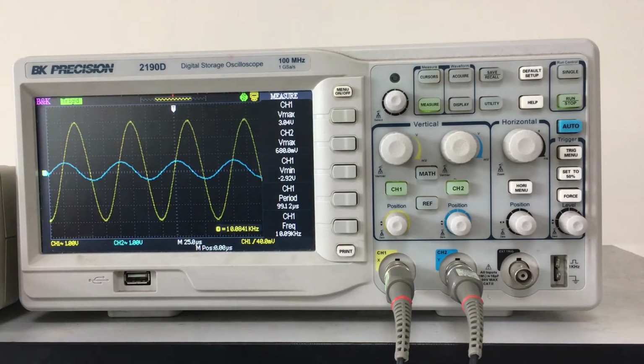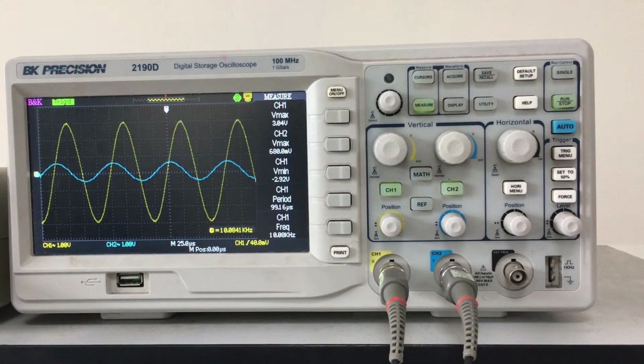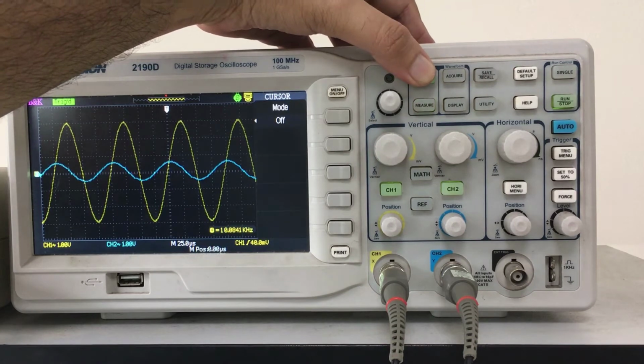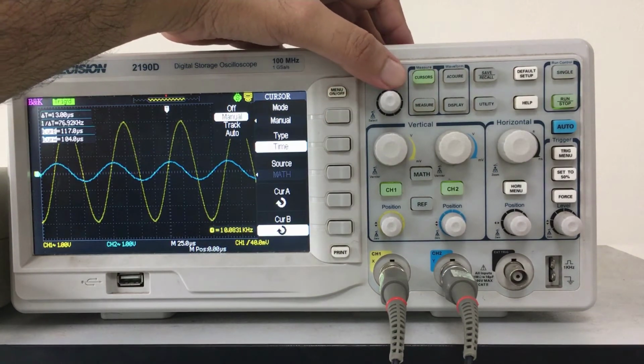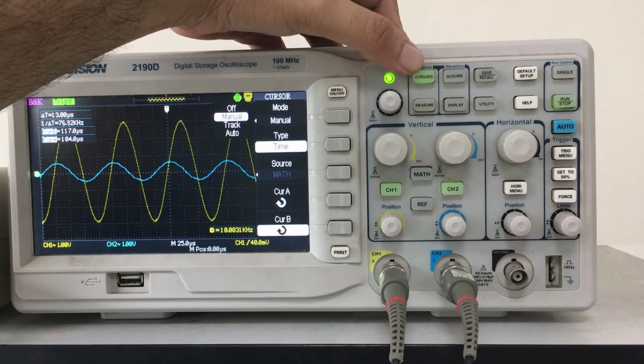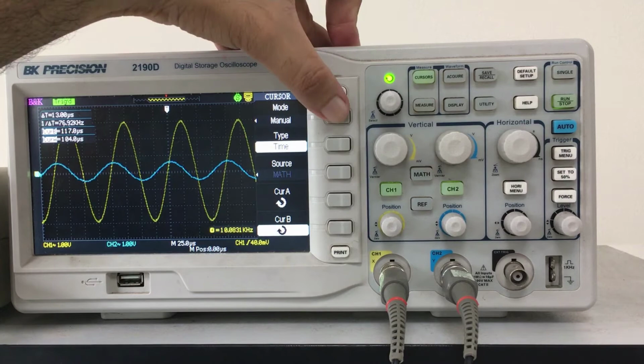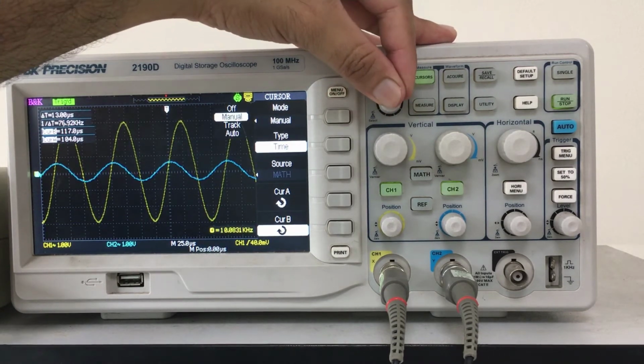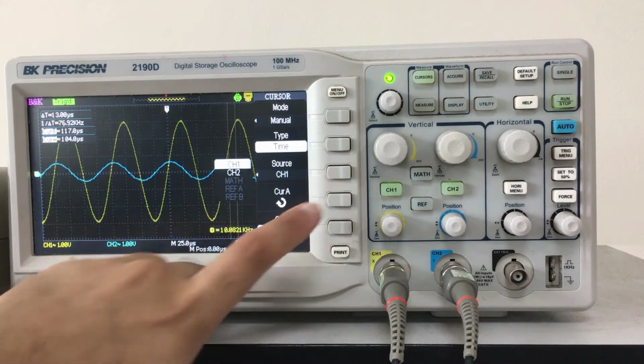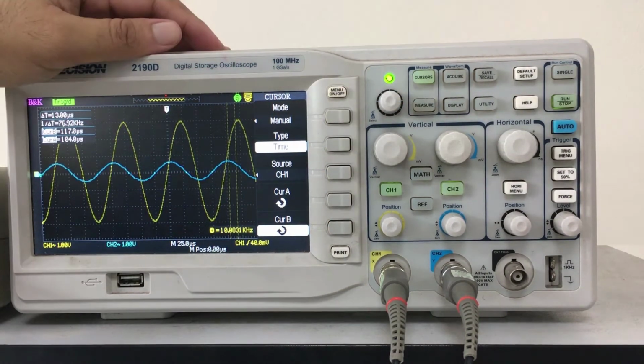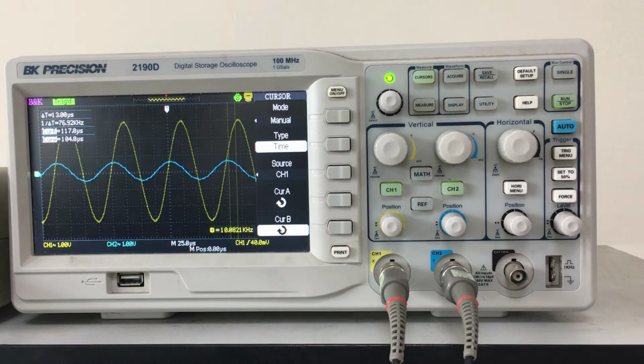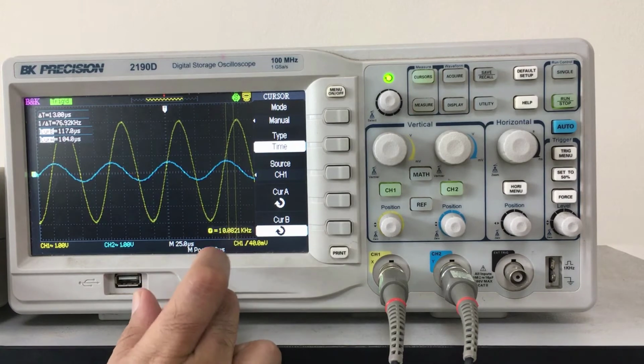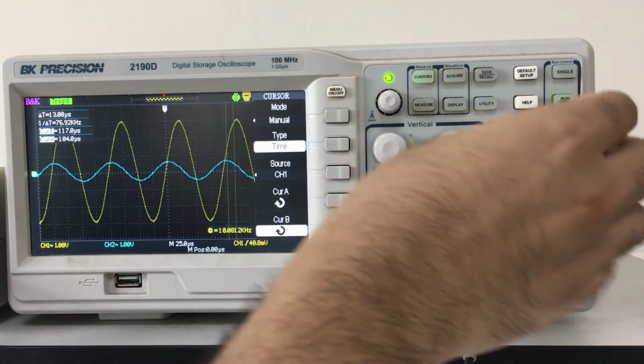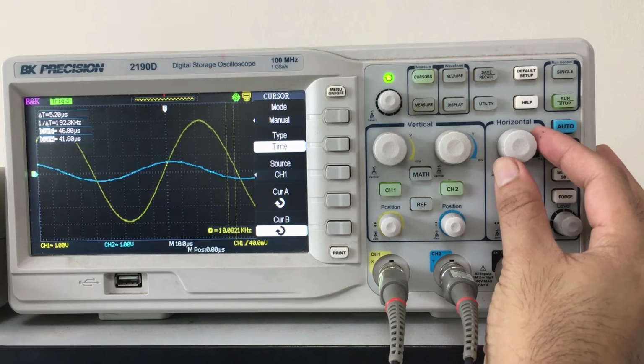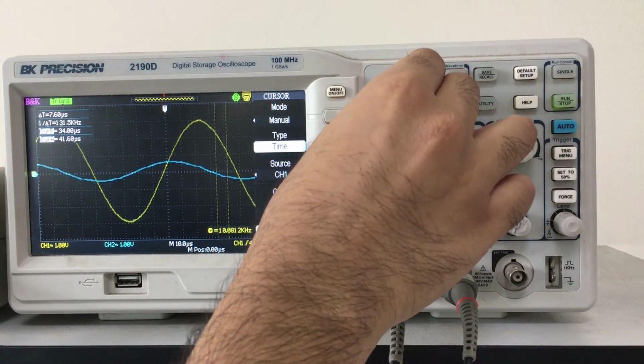Now we have to calculate the phase, and as previously we have to calculate the phase by using cursors. By pressing this cursor button, we have to turn it on. We press the cursor button and move the mode to manual, and the source should be channel 1 since we are taking the reading with respect to channel 1, or you can set it to channel 2 because the time scale is the same, so you will get the same reading. Now we can zoom in a bit by moving the horizontal, and now we can put it.